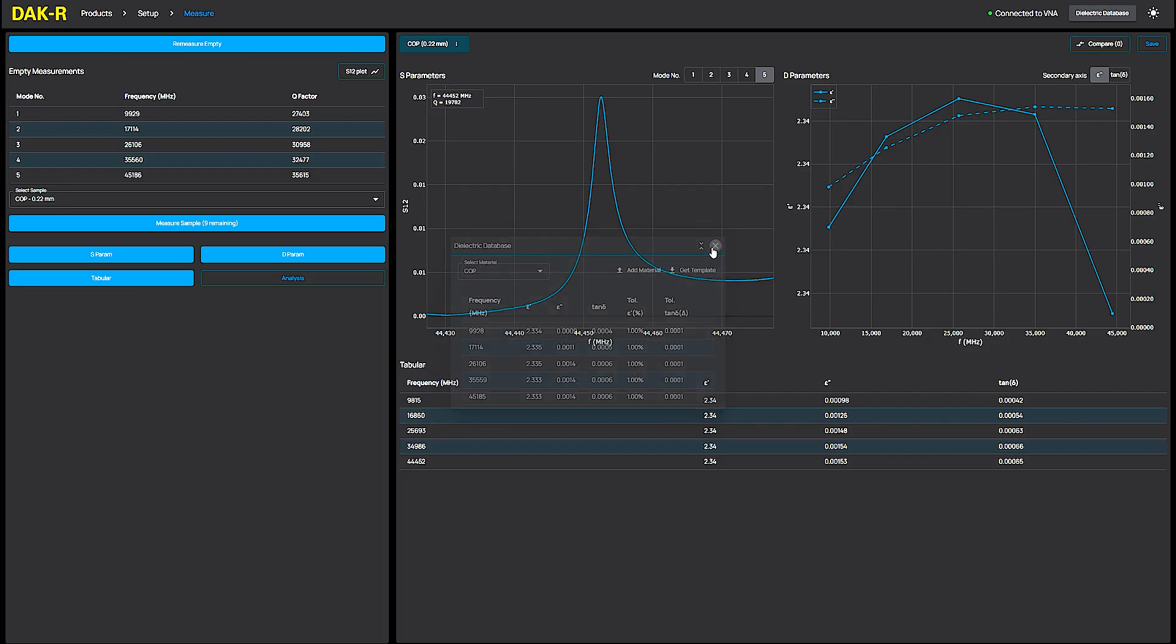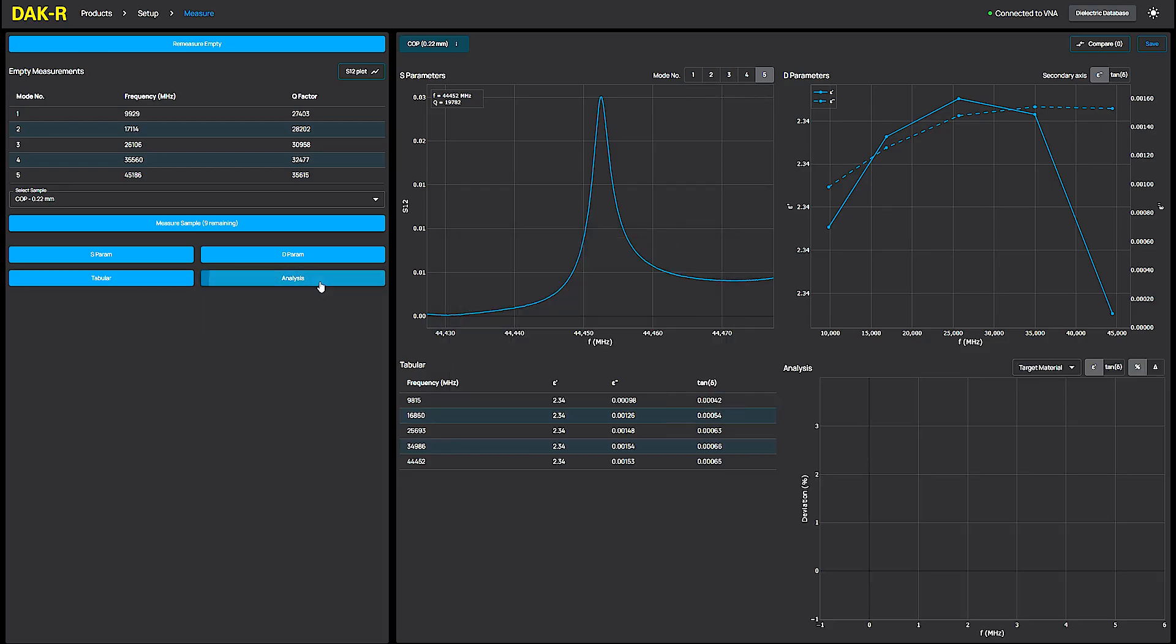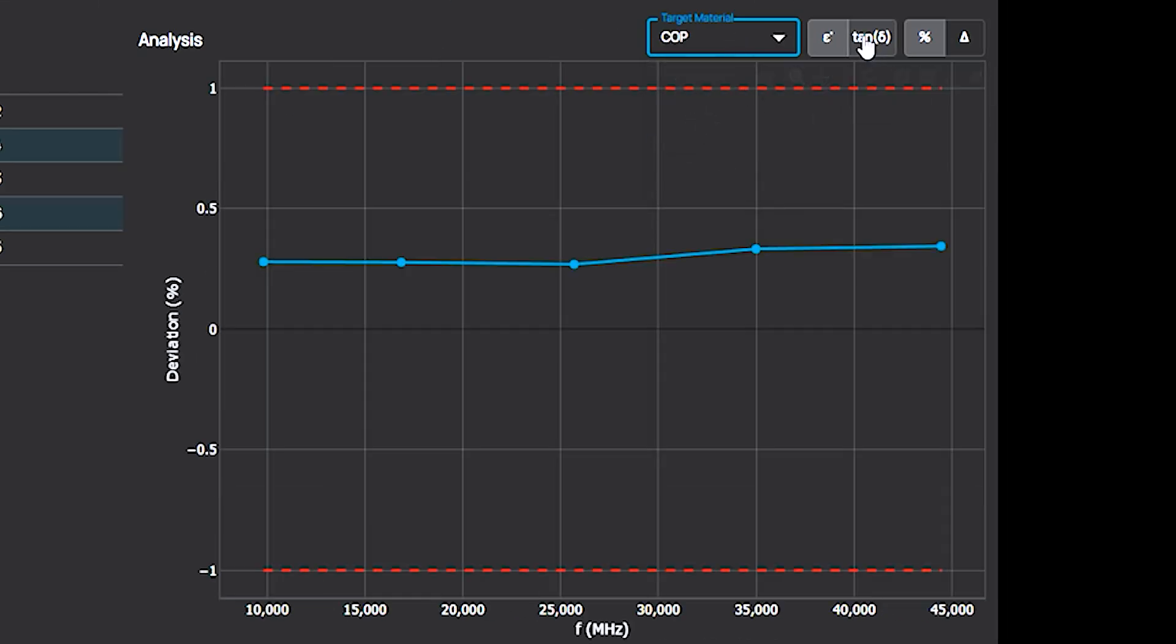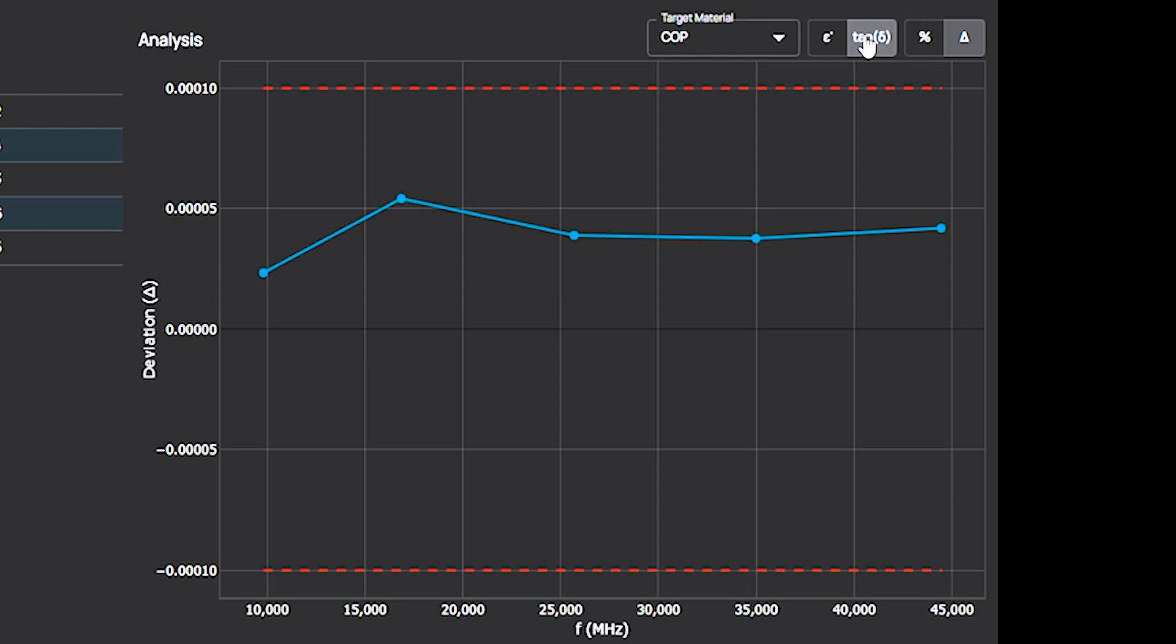I found another useful feature in the DAK-R software. To check my measurement deviations from the reference values, I can add my materials target data to the dielectric database, enable the Analysis button, and select the material from the drop-down list. This allows me to view deviations for both permittivity and loss.